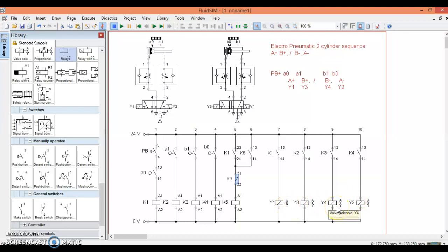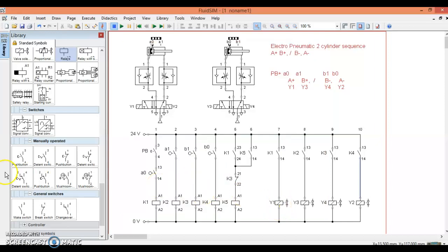So we had a problem here when Y1 came on, Y2 was already on. Now, if we know that K5 is going to be off in this part of the sequence, if we put a normally closed contact here, run K5.